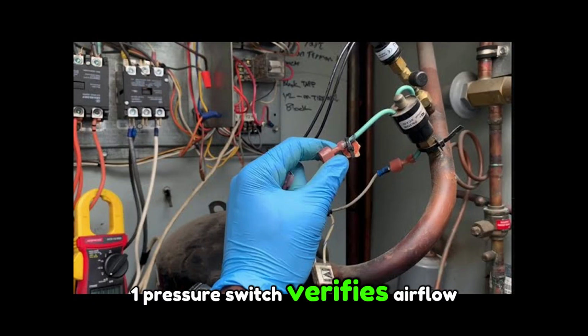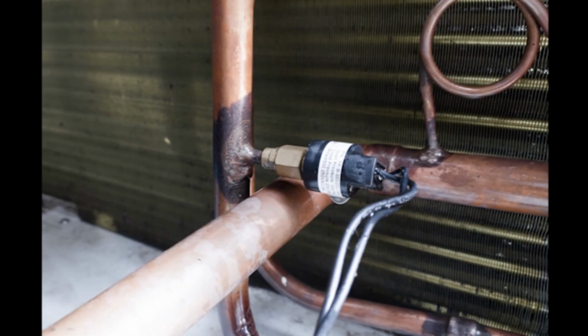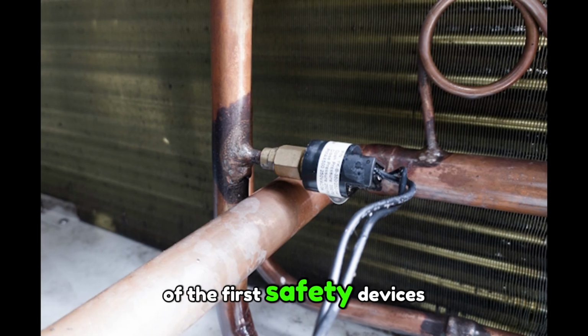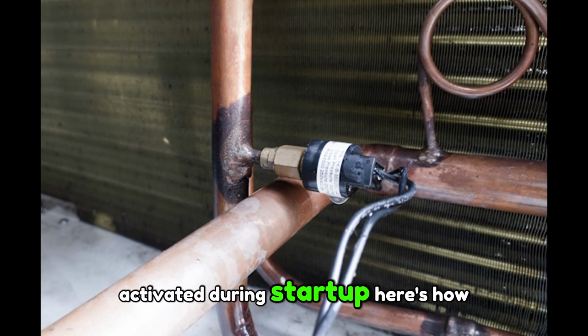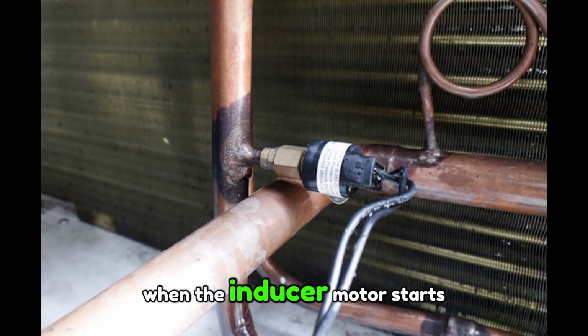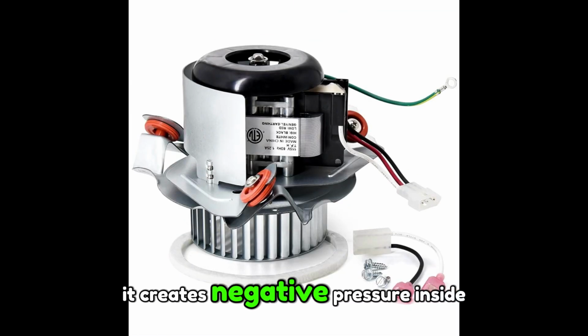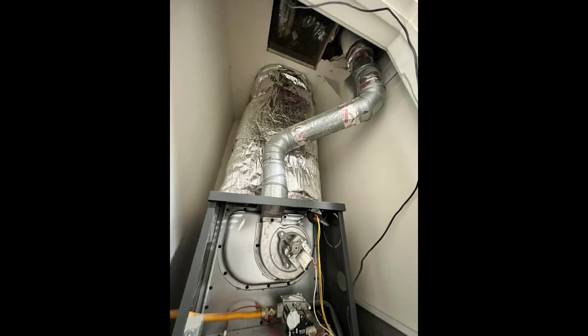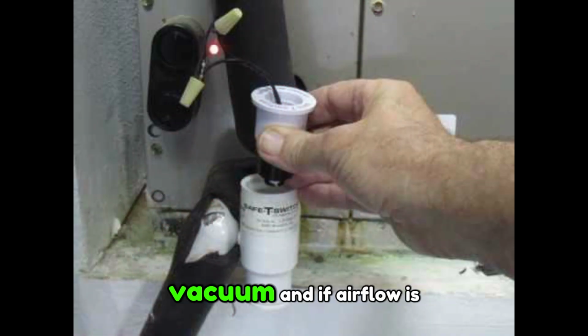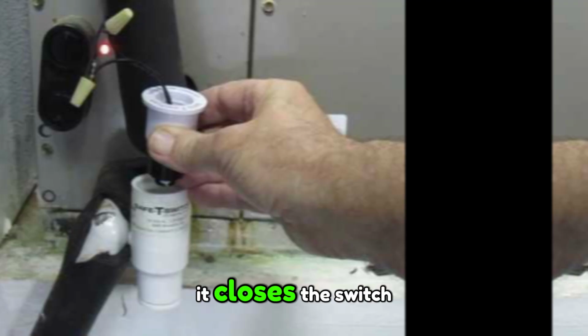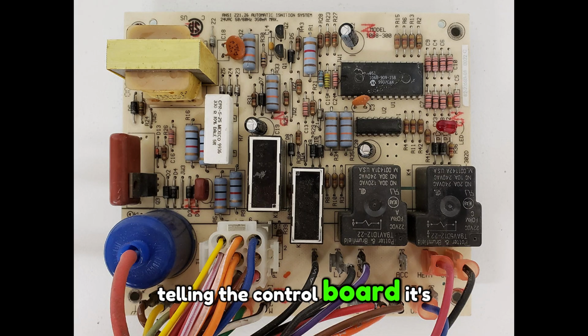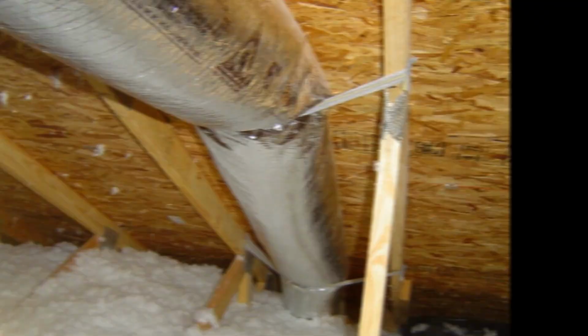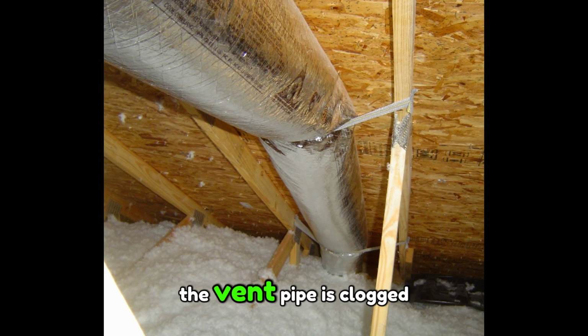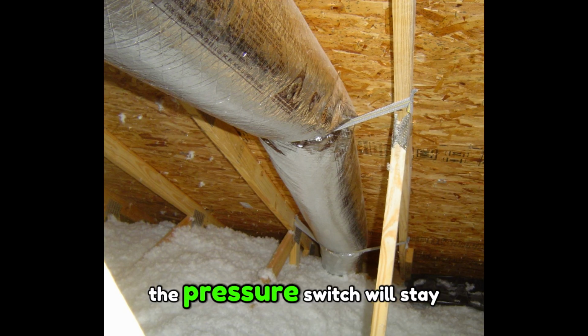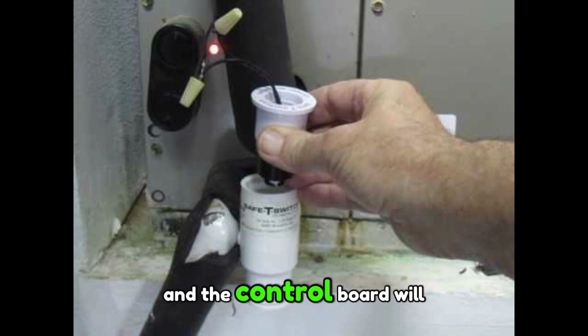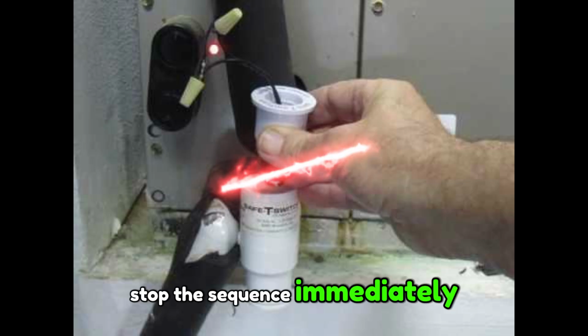1. Pressure switch verifies airflow in the vent system. The pressure switch is one of the first safety devices activated during startup. Here's how it works. When the inducer motor starts, it creates negative pressure inside the flue pipe. The pressure switch detects this vacuum, and if airflow is sufficient, it closes the switch, telling the control board it's safe to light the burners. If there's a blockage or the vent pipe is clogged or disconnected, the pressure switch will stay open, and the control board will stop the sequence immediately.